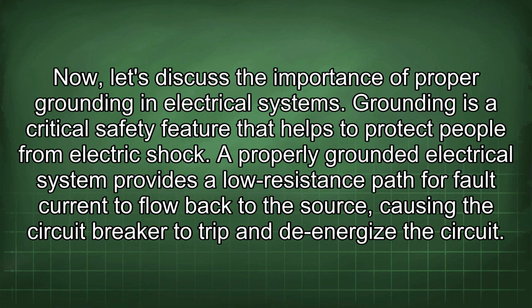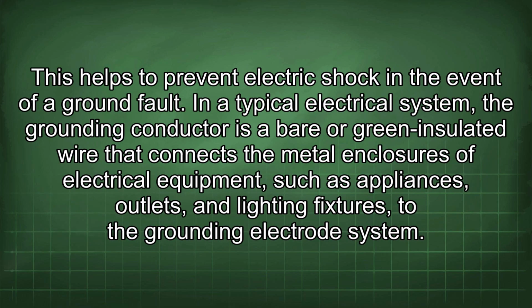Now, let's discuss the importance of proper grounding in electrical systems. Grounding is a critical safety feature that helps to protect people from electric shock. A properly grounded electrical system provides a low resistance path for fault current to flow back to the source, causing the circuit breaker to trip and de-energize the circuit. This helps to prevent electric shock in the event of a ground fault.